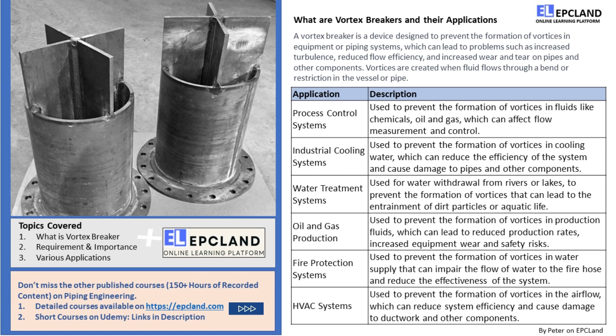Now, let's take a closer look at some of the applications of vortex breakers mentioned in the table. In process control systems, vortex breakers are used to prevent the formation of vortices in fluids such as chemicals, oil, and gas. These vortices can affect the accuracy of flow measurement and control, which can be a major issue in industries like chemical production. Industrial cooling systems also use vortex breakers to prevent vortices in the cooling water — without them, vortices can reduce cooling efficiency and cause damage to pipes and components. In water treatment systems, vortex breakers are used to prevent vortex formation when withdrawing water from rivers or lakes, as these vortices can lead to the entrainment of dirt particles or aquatic life, seriously affecting water quality.